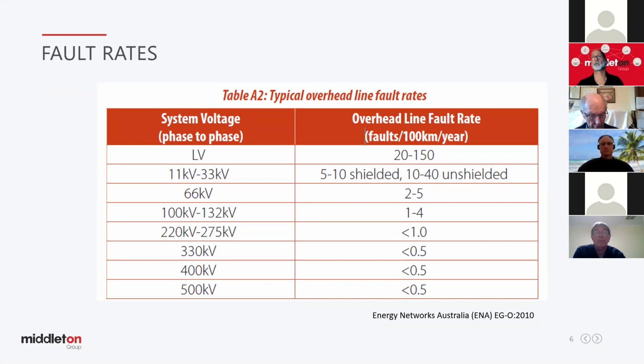So I'm in New South Wales. I'm going to say we've got 20 faults per 100 km per year. If we divide that by 100, we've got 0.2 of a fault per year. But if we've got 10 feeders that could likely fault and therefore cause EPR at the zone substation that's bonded to your house, you could get a hazardous voltage on your house. So in this case it could be 2 times a year or 20 times a year. It's more often than many people think that you may have a hazardous voltage transferred to your taps or showers.